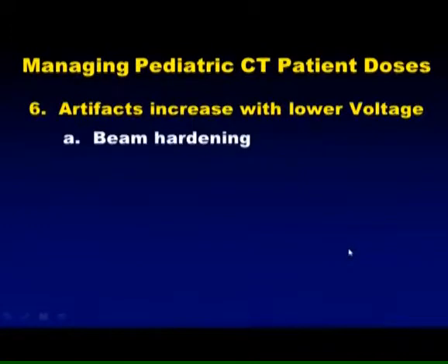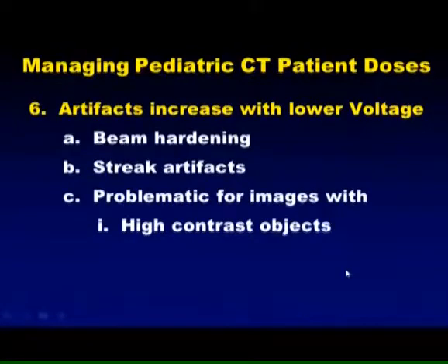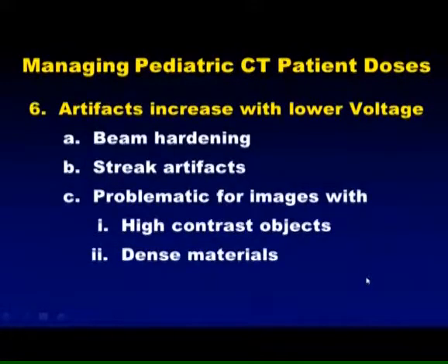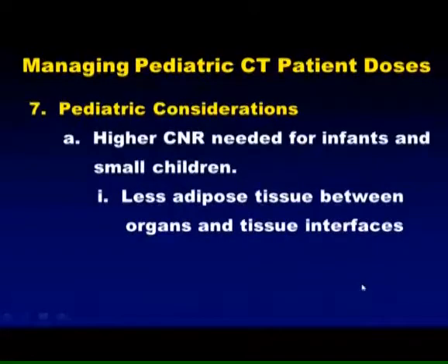Okay, beam hardening. With lower kV, I'm going to tend to have more streak artifacts. It's going to be more problematic if I have high contrast objects, dense materials, in the patient anatomy. So there are trade-offs in lowering the kV.